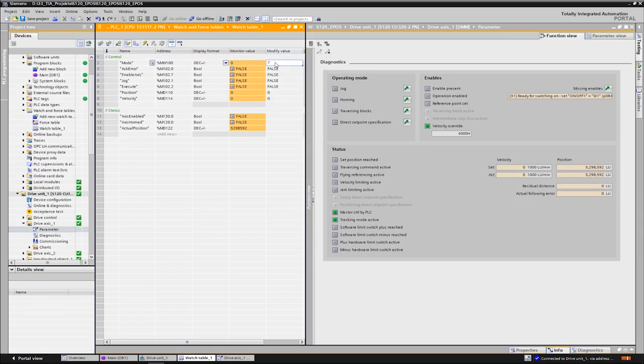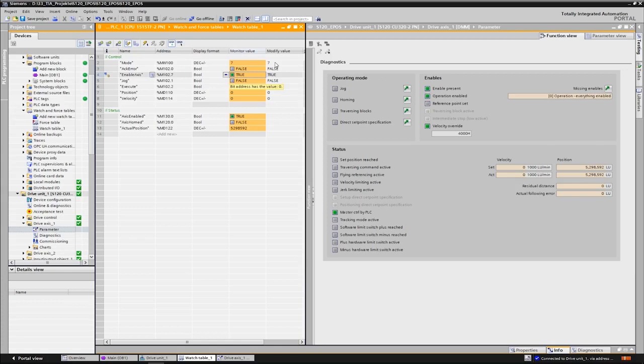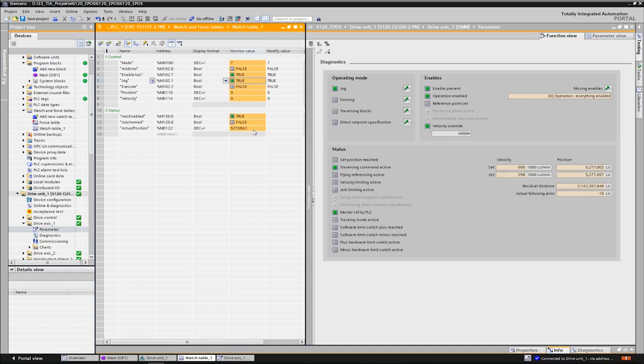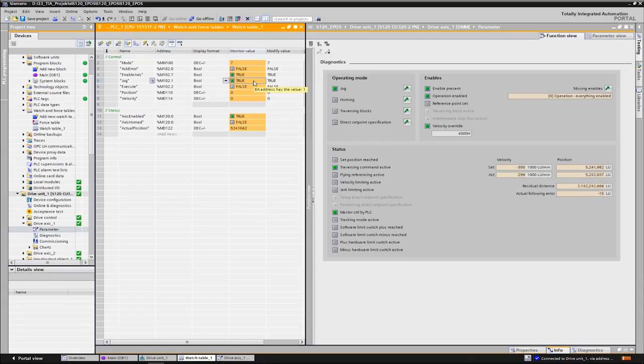For this we select mode 7. All modes are described in the manual of the block. Now we switch on the axis via the enable axis command and start the jog command. We can observe the actual position and see that the axis is now moving. As long as the jog command is pending, when deselected, the axis stops.